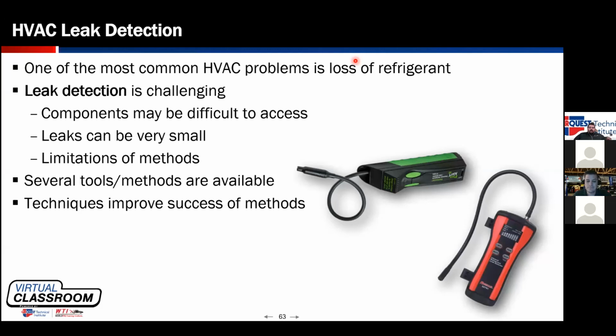I always say, and the guys tend to laugh, every leak detector has a personality. You have to start becoming comfortable with your leak detector, figuring out what will make it false trigger, and how you need to work with it in order to get the best out of it. For example, I have 3 leak detectors that I use in the shop. I know that 2 of them will false trigger if I bump the tip. The third one will not. So I have to be mindful of that while I'm using the detector.